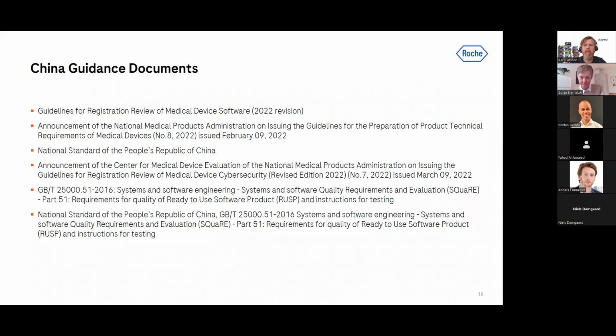All right. And I mean, the elephant in the room here, in order to submit a product to China, do I need to speak Chinese? No, you don't need to speak Chinese. So you need to have your submission documents translated. And I think the issue might be if you don't have somebody speaking Chinese, you may have some issues when answering their feedback. So I would recommend to have at least somebody in your quality regulatory or R&D organization being able to speak Chinese, because what's also possible after you submit it, you may have telephone conferences with them, and these unfortunately need to be in Chinese. Wow.